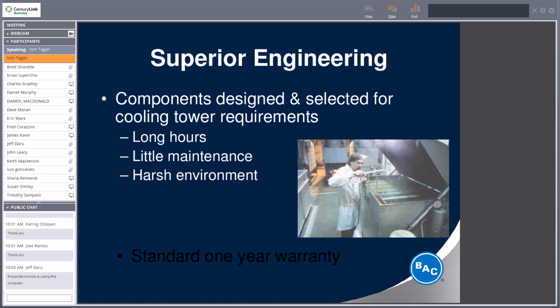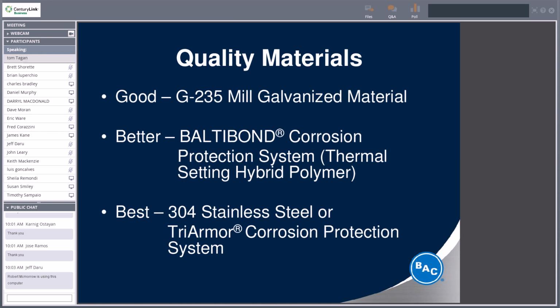Typically, the engineers in New England who we deal with all put a stainless steel cold water basin on their towers. It's the most expensive component in your open cooling tower. It's also the most expensive to replace because generally now you're talking about getting a crane. So when at all possible, if you have any influence, you definitely want to make at least your cold water basin stainless steel. The materials, G235 galvanized steel has become the standard. A little bit more propaganda. BAC has a Baltibond corrosion protected system, but we can go to 304 stainless steel that everyone does. We're starting to see a lot of all 304 stainless steel cooling towers, specifically for state-owned properties, university-type projects, where owners are going to be there for a number of years. We're starting to see a lot of people opt for the all stainless steel to prolong the life of the tower.